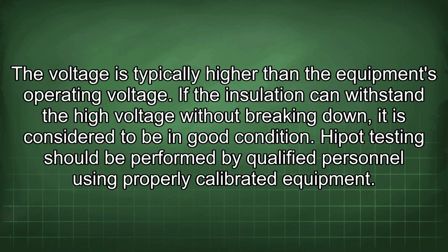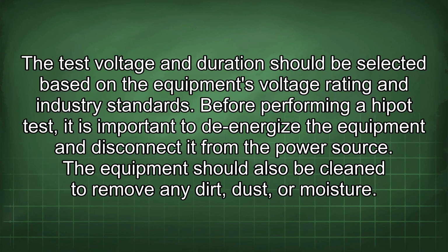Hipot testing should be performed by qualified personnel using properly calibrated equipment. The test voltage and duration should be selected based on the equipment's voltage rating and industry standards. Before performing a hipot test, it is important to de-energize the equipment and disconnect it from the power source. The equipment should also be cleaned to remove any dirt, dust, or moisture.